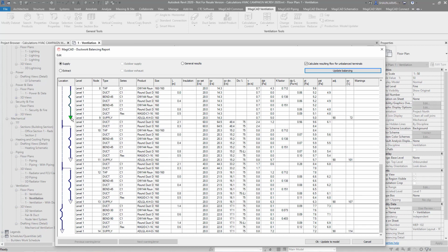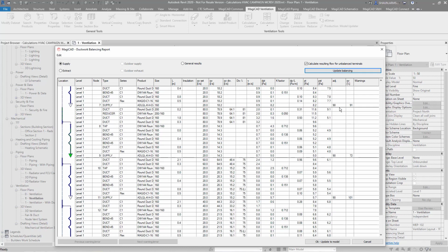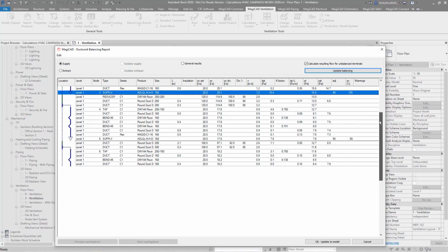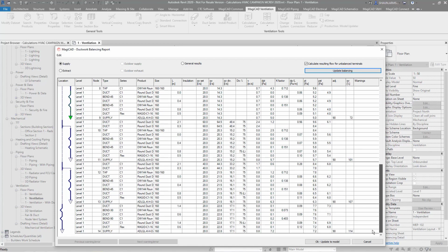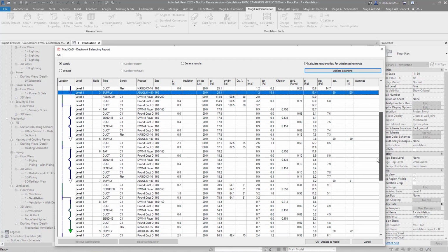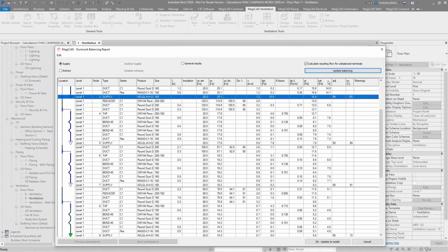There is actually a VCD within these grills, and this is where they are adjusted. So it's 90% adjustment there. But what you might need to do is go ahead and add more VCDs to the system to help equal the flow out between the whole of the system. And it's also gaining pressure here from the static pressure, where the system rises and drops. So it's taking and increasing the pressure as that happens.